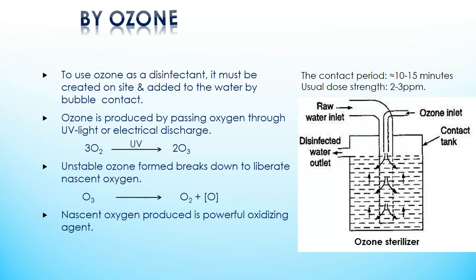Disinfection of water by ozone. Ozone is an excellent disinfectant but highly unstable. Hence, it must be created on site and added to the water by bubble contact. Ozone is produced by passing dry and cold oxygen through ultraviolet light or silent electric discharge.